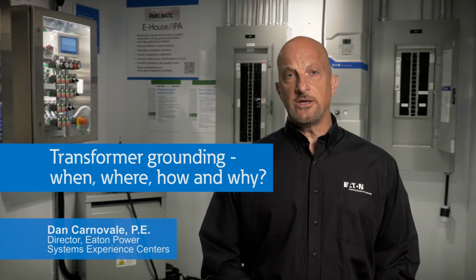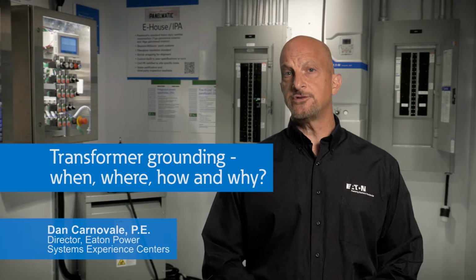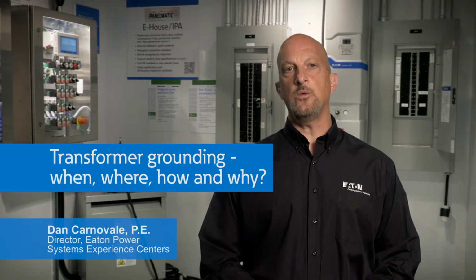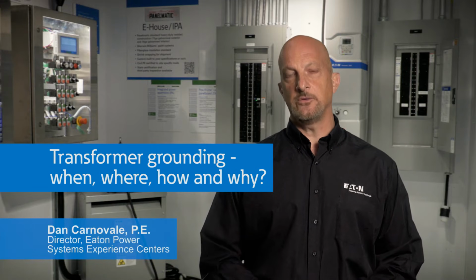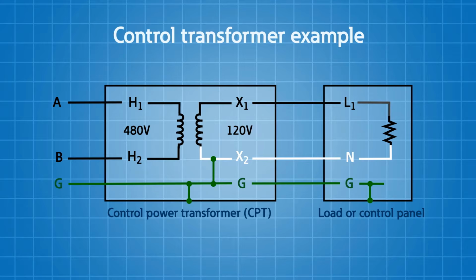With respect to grounding, transformers are often an area of concern and discussion regarding when, where, how, and why to ground the transformer. This is a simple single-phase example of a transformer like a 480 to 120 volt control power transformer. Considering the secondary windings, one of the two legs, typically X2, would be connected to ground.